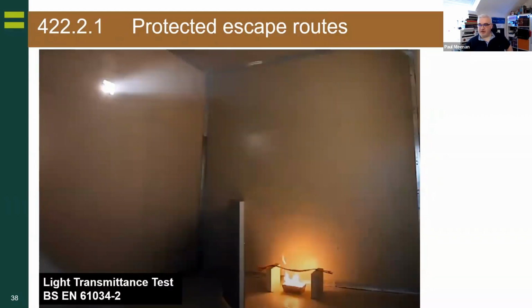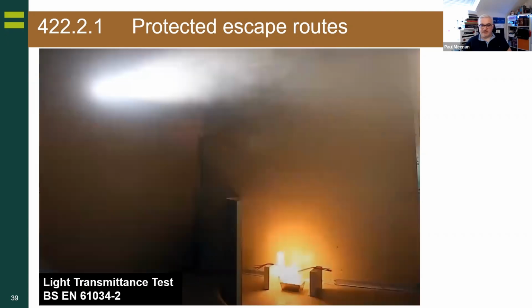Here we go. Apologies. So protected escape routes. One of the things that we just briefed on was the light transmittance test. So if we look at 61034, what it is basically, you can see at the bottom of the photo there's a cable 1 meter length under test, and we're looking for the emissions, namely smoke for this. Now, they'll test this for a number of minutes, and after a certain set minutes, can you still see 60% of the light? And there is a monitor on the right hand side that reads the light output. And it's literally as simple as that.